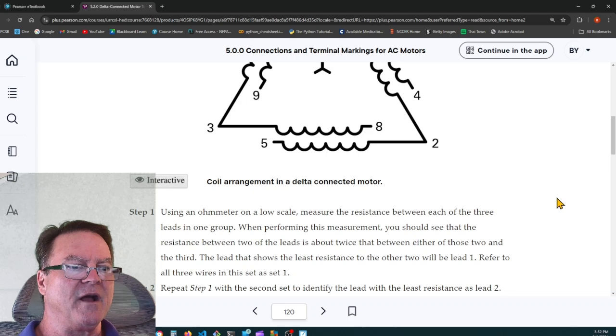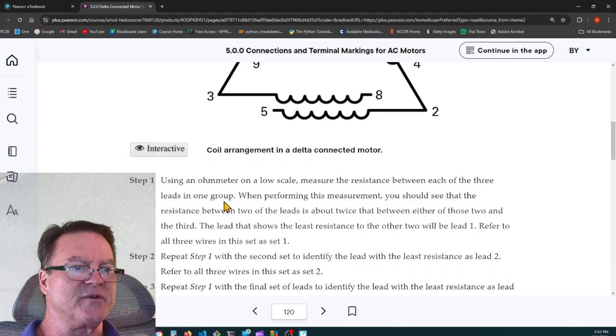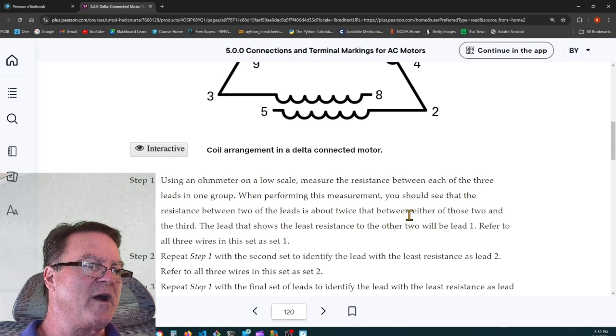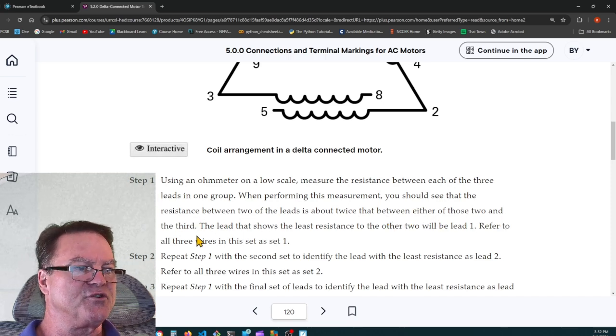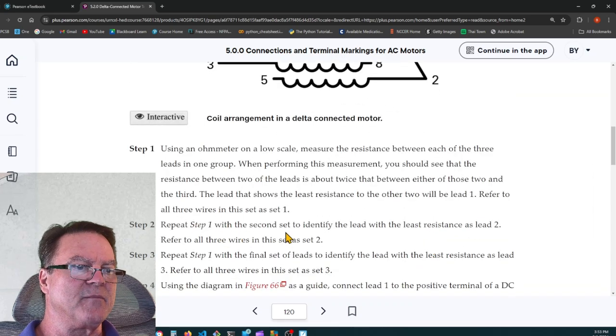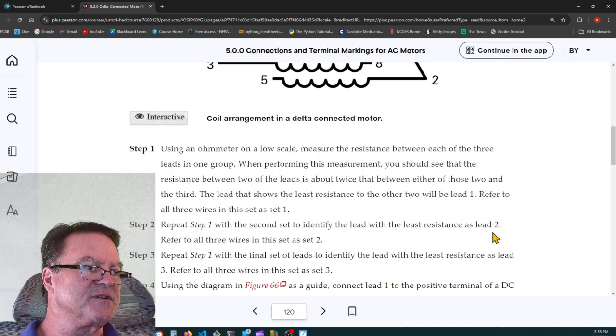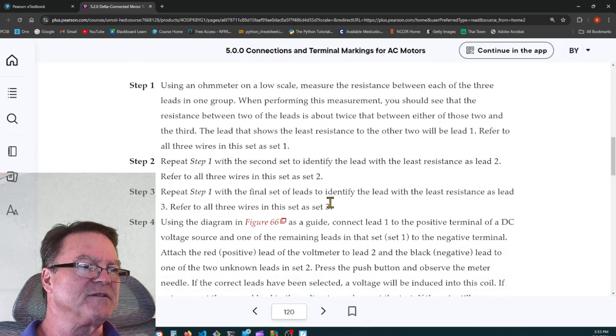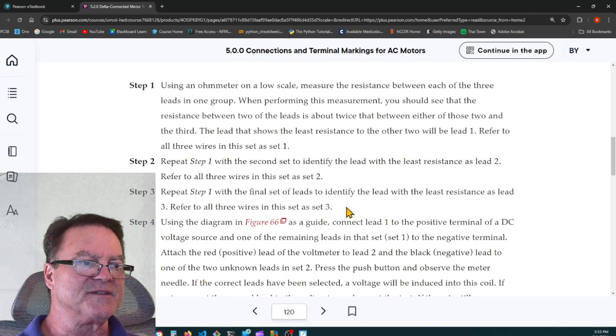So the same thing. Using an ohm meter on a low scale, measure the resistance between each of the three leads in one group. When performing this measurement, you should see that the resistance between two of the leads is about twice that between either of the other two and the third. The lead that shows the least resistance to the other two will be lead 1. Refer to all three wires in this set as set 1. Repeat step 1 with the second set to identify the lead with the least resistance as lead 2. Refer to all 3 wires in this set as set 2. Repeat step 1 with the final set of leads to identify the lead with the least resistance as lead 3. Refer to all 3 wires in this set as set 3.